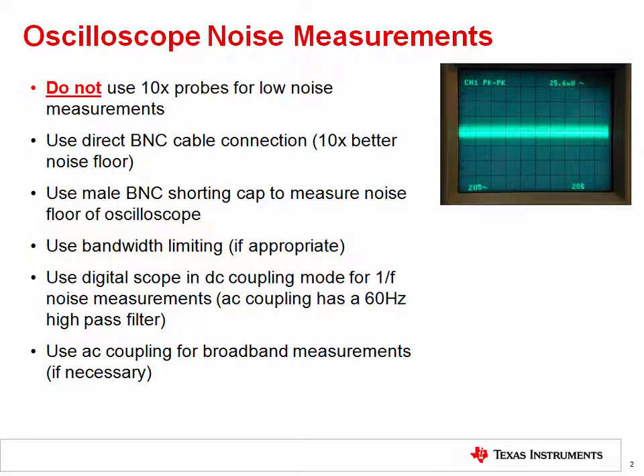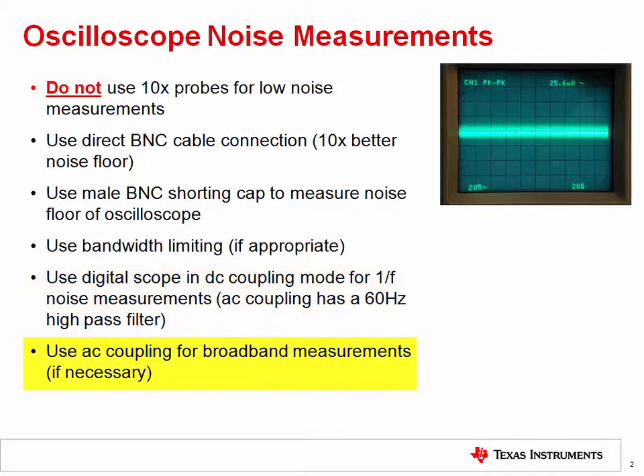1/f noise is normally measured from 0.1 to 10 hertz, requiring a DC-coupled digital scope set on a very large time scale, typically one second per division. It is important to make sure that the scope is DC coupled for 1/f measurements, since the typical built-in AC coupling circuit uses a 60 Hz high-pass filter, which doesn't properly show flicker noise. For broadband noise measurements, on the other hand, you can use AC coupling, which eliminates the DC offset and allows for the best measurement range.